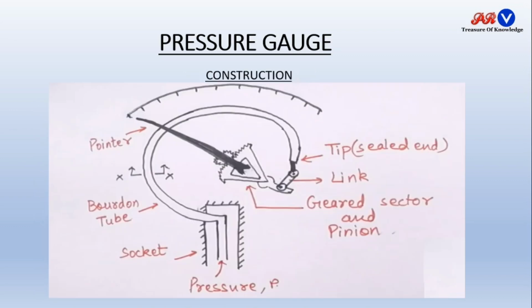This is the diagram for C-type Bourdon tube or C-type pressure gauge. So pressure to be applied is given here. It is an open end of the Bourdon tube, and this end is the sealed end tip, which is closed at the other end. So socket is used to support this tube, Bourdon tube. This is our Bourdon tube. This is the pointer and scale arrangement which is calibrated in terms of the pressure.